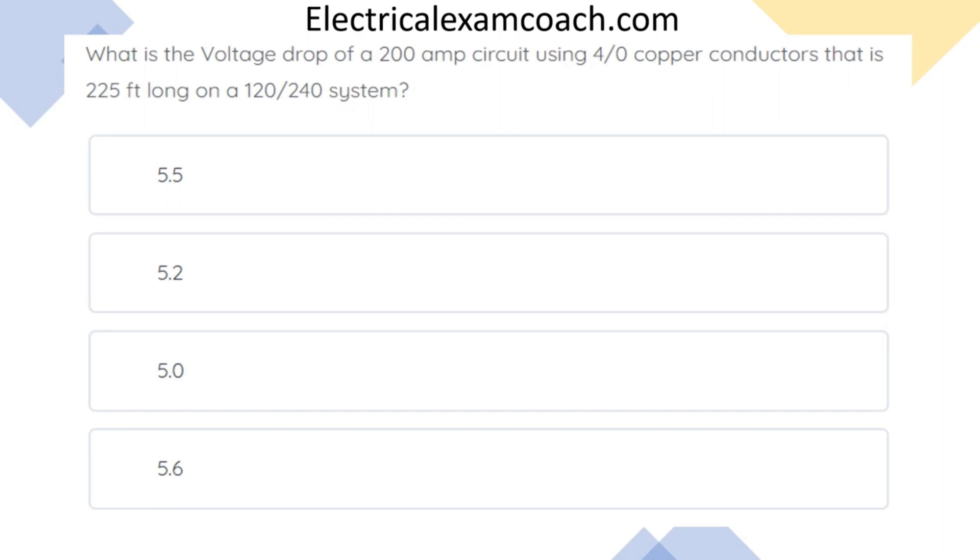What is the voltage drop of a 200-amp circuit using 4-aught copper conductors that is 225 feet long on a 120-240-volt system?